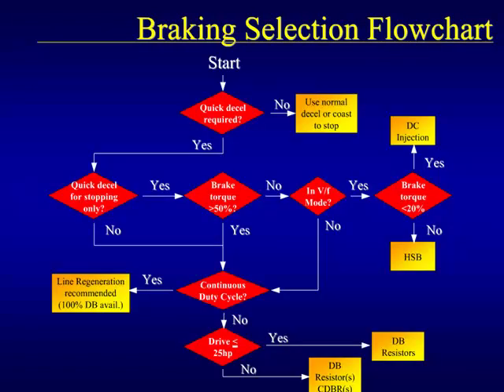Here is a flow chart that can be used as an aid when determining the appropriate type of braking method to use. This is a general recommendation and actual braking solutions depend on issues such as size constraints, complexity of the solution, acceptable heating, power quality, and cost. The appropriate braking solution is shown in yellow. Note that there are two dynamic braking solutions shown in the bottom right-hand corner. If the drive is less than or equal to 25 horsepower, only dynamic braking resistors are required. If the drive is over 25 horsepower, both resistors and transistor units are required.